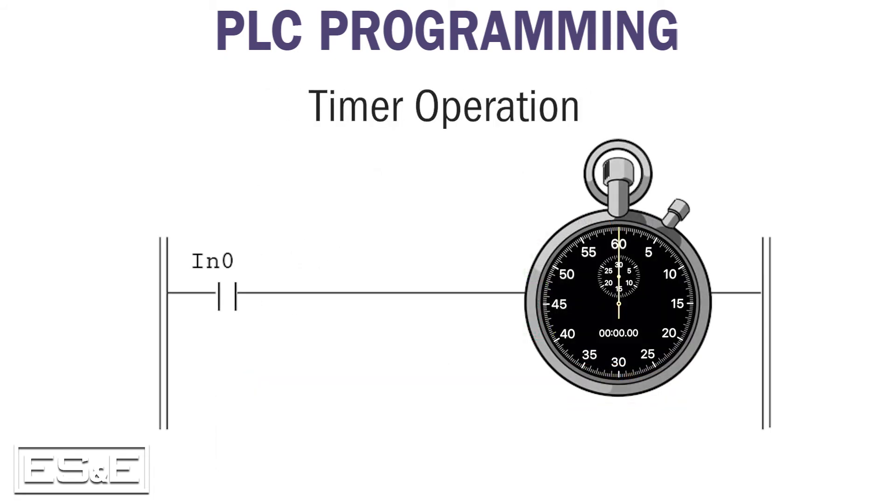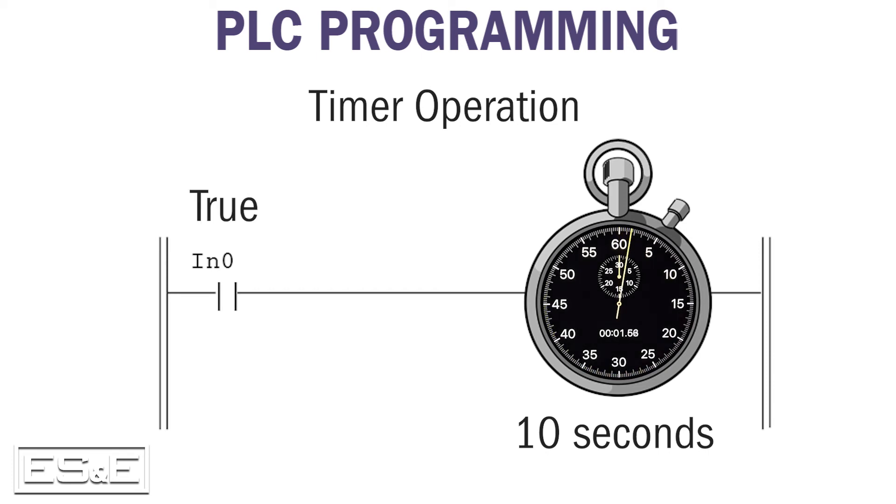A timer is the most complex instruction we will cover. As an example, let's say a motor is required to run for 10 seconds and then turn off. In that case, the timer preset value will be 10 seconds. As long as the input condition solves true, the accumulation value will increment until it equals the preset value. At that point, the timer done bit, also referred to as the DN bit, will change from 0 to 1. When the input condition for the timer solves false, the timer accumulation value resets to 0, and the done bit is also set to 0. This can happen before or after the accumulation value equals the preset value. Understand there are multiple types of timer instructions that operate differently than what I just described.